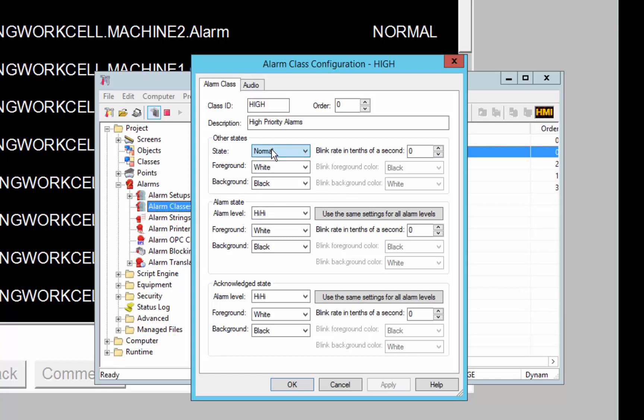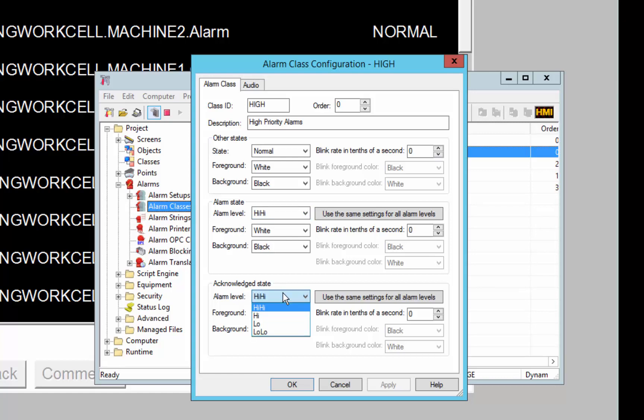So you can set up the normal and unavailable state to have its own colors and blinking scheme. You can set up the different alarm levels to have different colors and blinking, and the acknowledged state as well can be configured separately. You also have the ability to set the order of the alarm class such that if you sort your alarm viewer by class order, it will respect the order that you set in each class.